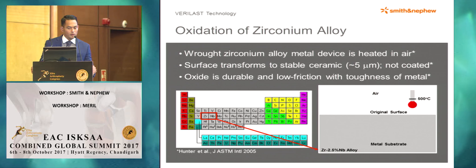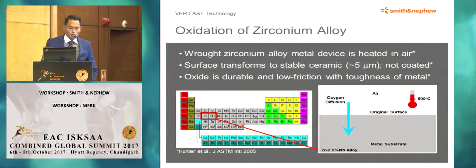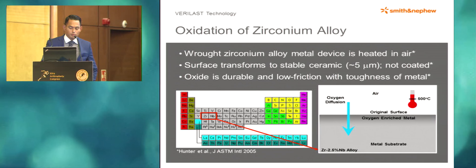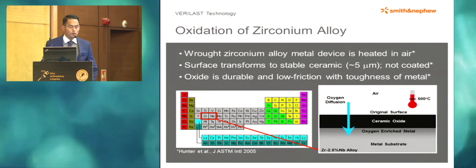What is the process of developing Oxinium? It's a wrought zirconium alloy that is heated in air. The surface transforms to a stable ceramic. Smith & Nephew will tell you that they don't like to use the 'coated' terminology — the surface actually transforms, so it's not a ceramic coating — a very important distinction. Oxygen is diffused on the original surface, becoming a stable ceramic, and you get a uniform ceramic oxide layer that is durable and low friction, with the toughness of metal.